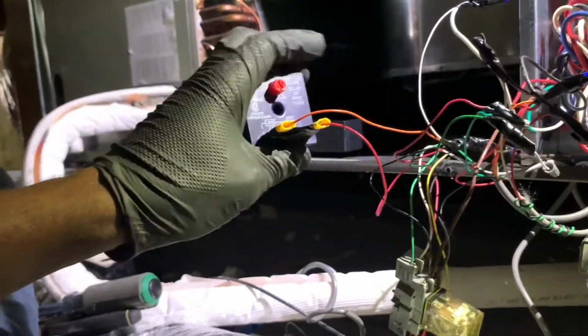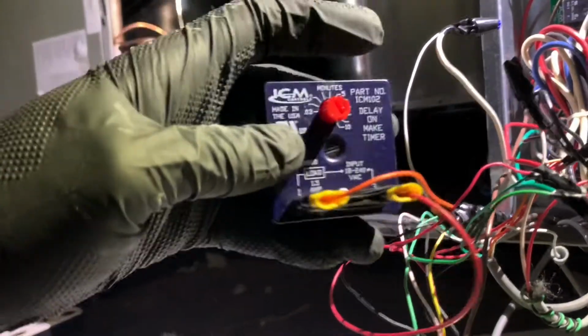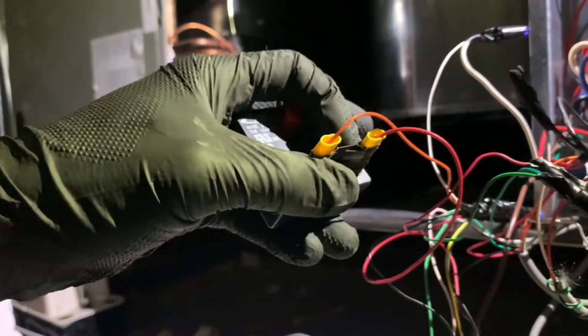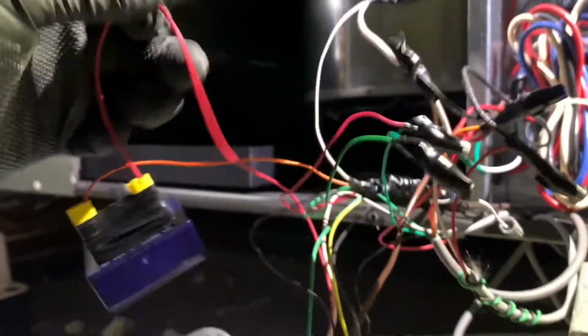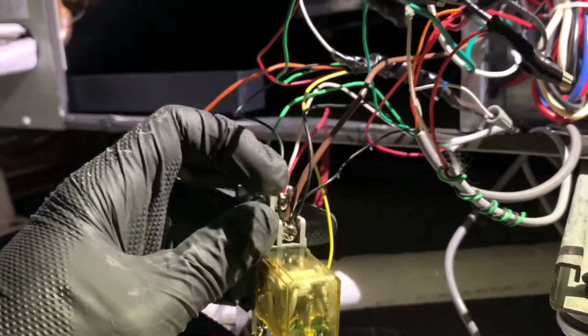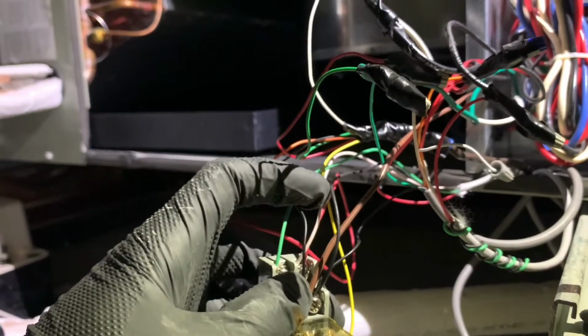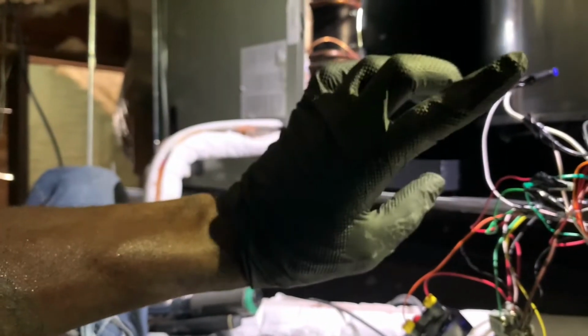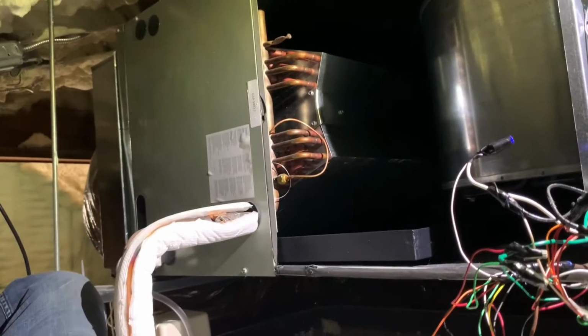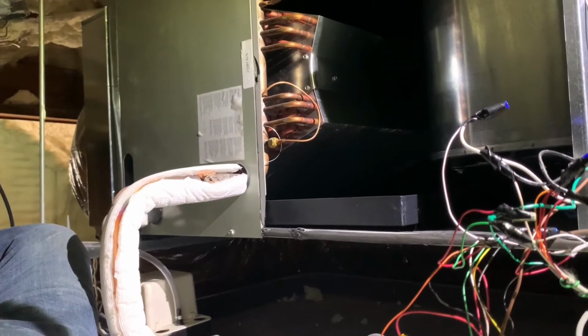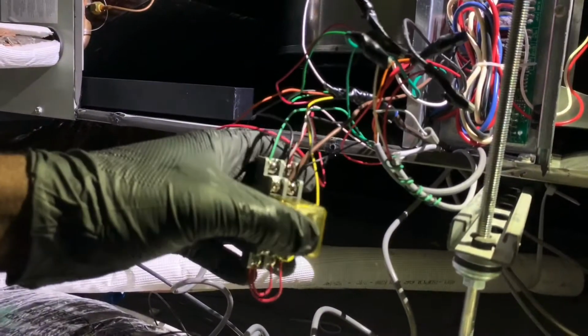And then W2, whenever that comes on, I give it a 10 minute delay on this time delay right here, before it will pass 24 volts through this red wire, which goes back to this relay right here, this terminal, which is the same white wire going outside to my condenser for Y1, or cooling. So on the heat pump, if you activate only Y or Y1, just Y without the reversing valve, or without O, then that's heating. So if the thermostat calls for a second stage, it will wait an additional 10 minutes, because the heat pump section of this is not the primary source of heat. That's how I want it. I don't know if the thermostat can do this. I didn't research that. I just simply put a relay here that will do that for me.